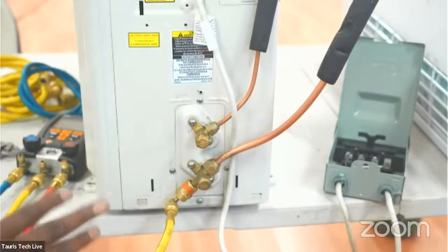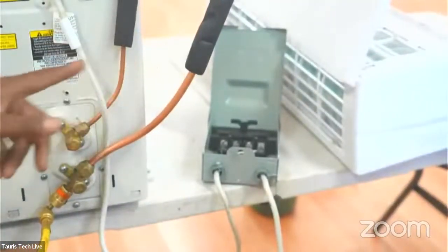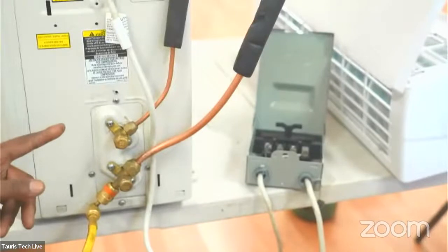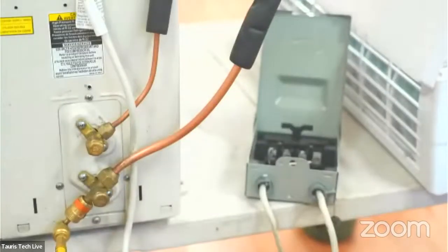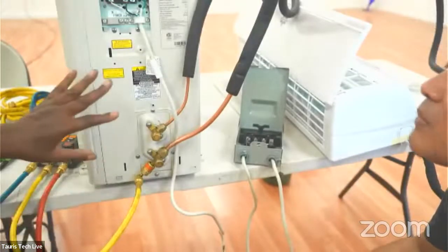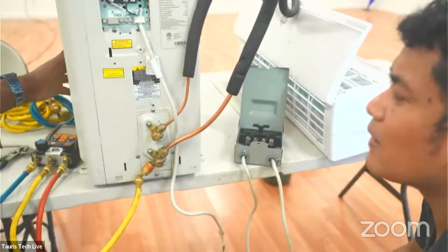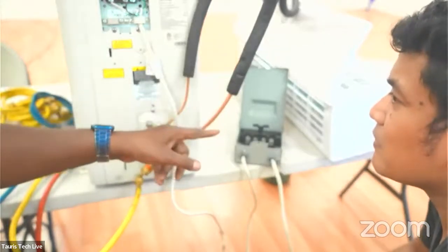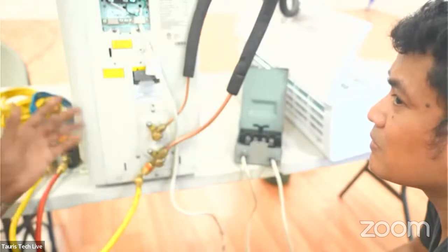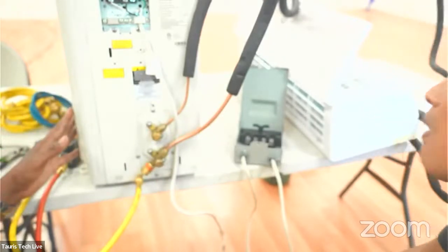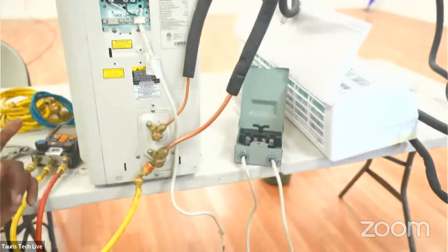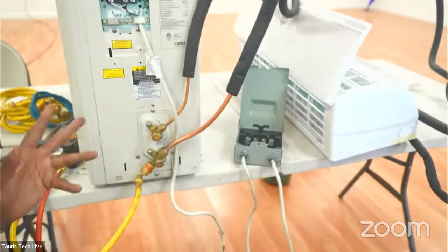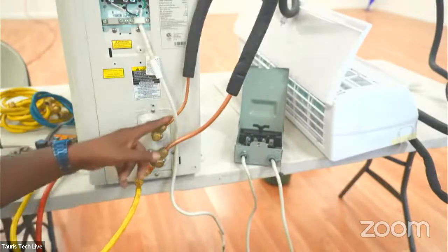So what we're testing, this is what people don't always understand, right? You have your indoor coil, you have your outdoor coil. It's changing roles when we go from heating to cooling, right? So in cooling mode, this is the condenser, the high pressure is out here. In cooling mode, that's the evaporator, it's low pressure. But then in heating mode, it switches. So then this becomes the evaporator, and that becomes the condenser. So what happens is in cooling mode, you have high pressure liquid.